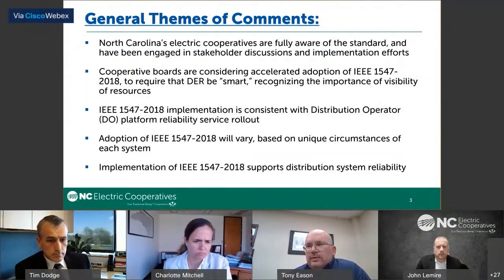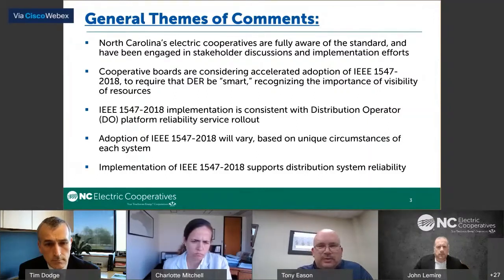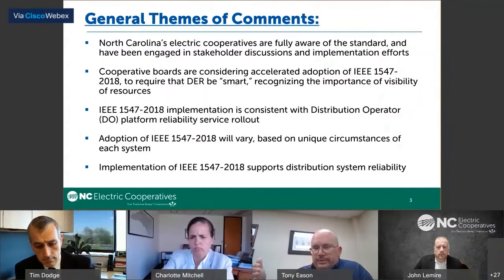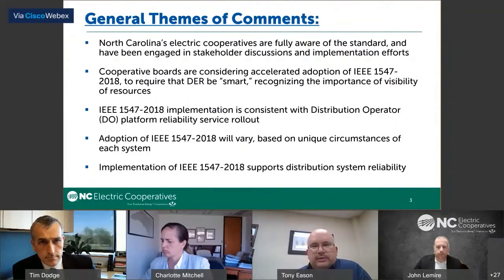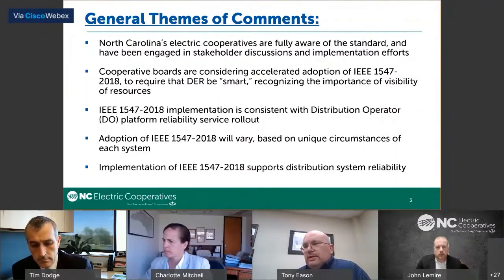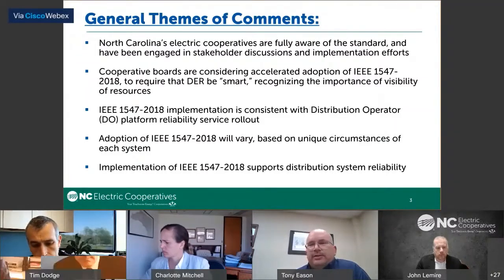One of the reasons why PD would like to adopt 1547 is it clearly defines several things: trip versus cease to energize, which are different things. It clearly defines when the DER must meet these parameters at the PCC, the utility side, or at the point of connection, right at the DER terminals. That was always a question in the past, but there's a clear delineation of size and output that gives us guidance and cleared up a lot of non-standard discussions. Coupled with the interoperability capabilities, it makes it attractive to adopt 2018.